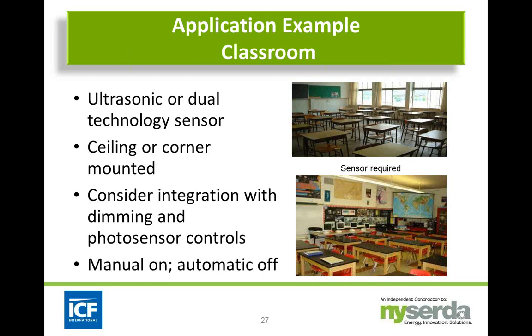We'll look at more applications of that in a moment. You want to do this as manual on and automatic off, but still allow the teacher to have control to turn the light switches off. Manual on because many classrooms have glazing around the perimeter or skylights, which allows some light into the space, so you may not necessarily need the lights on immediately when you come into the room.